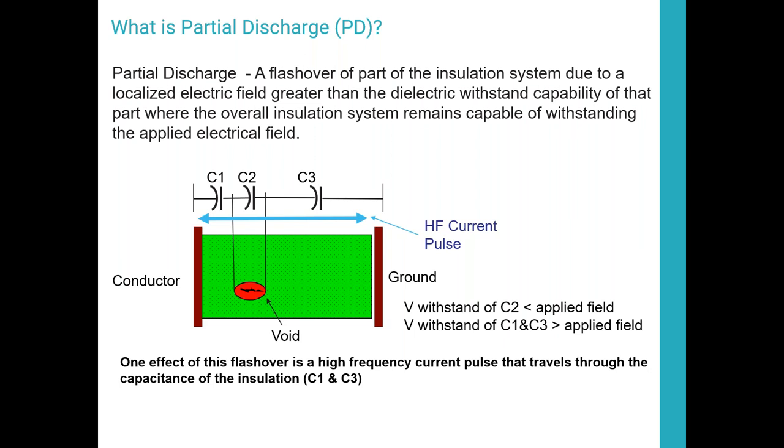There's another question. With regard to VLF cable testing, would using the UltraTEV Plus 2 with the RFCT connected to the shield return in conjunction with traditional VLF testing practices improve techniques? Well, the RFCT and then the EA equipment, such as the UltraTEV Plus 2, is designed to only work at power system frequency, so either 50 hertz or 60 hertz. It won't work at the VLF frequencies, which are 0.1 hertz or 0.01 hertz.